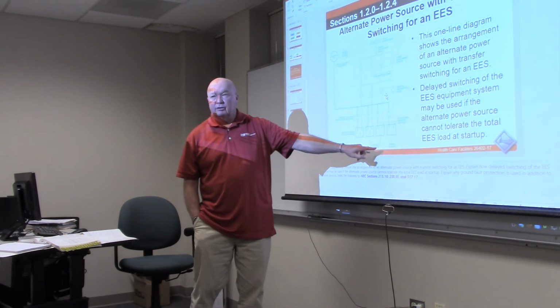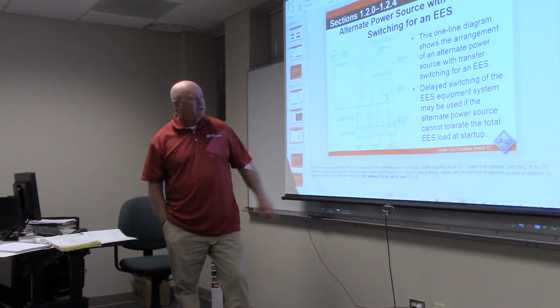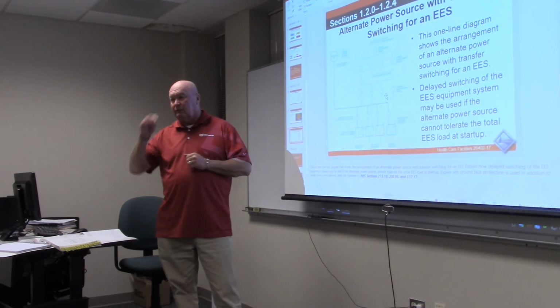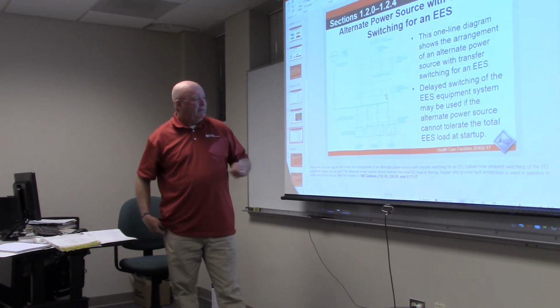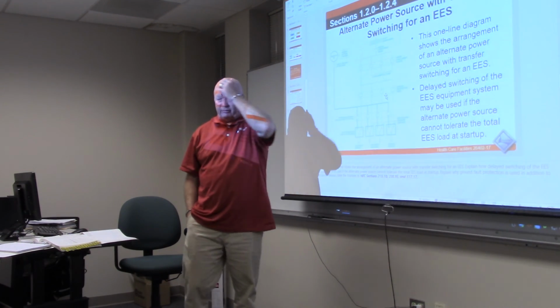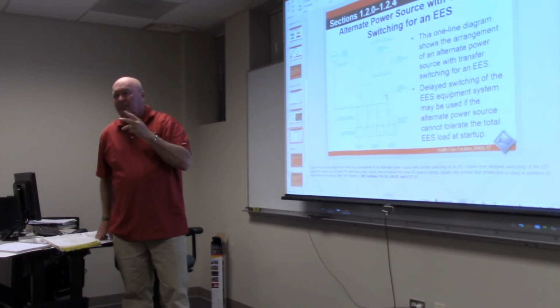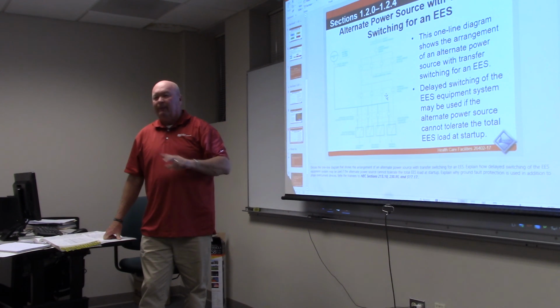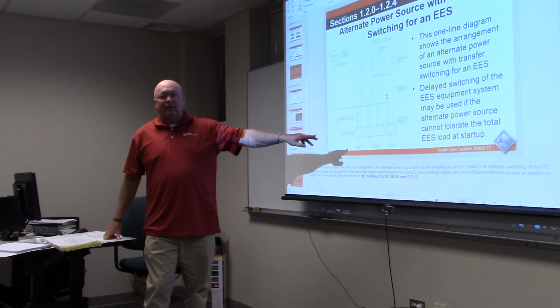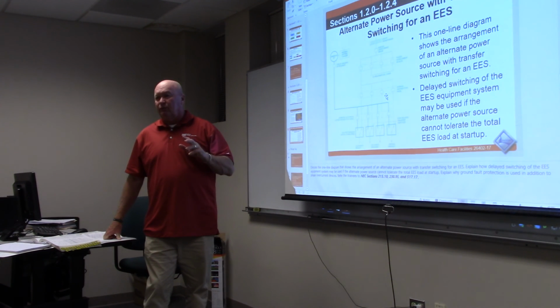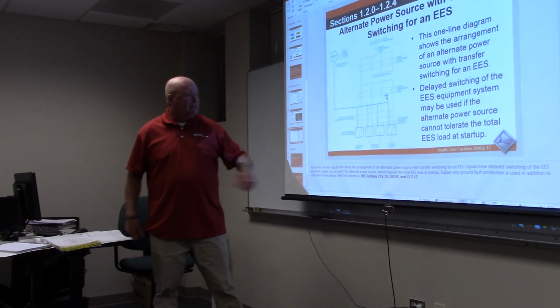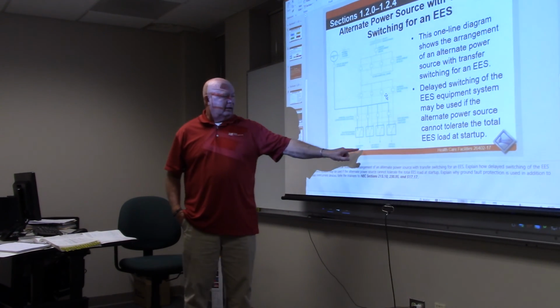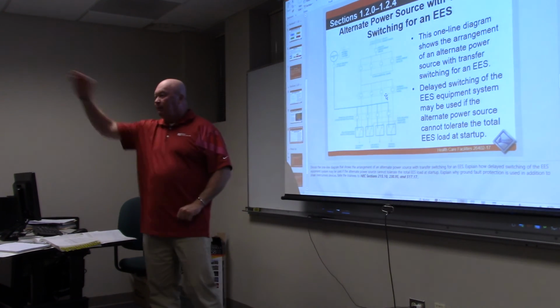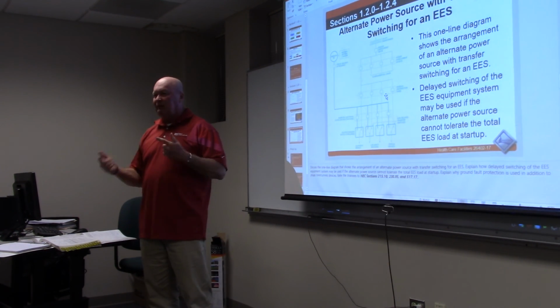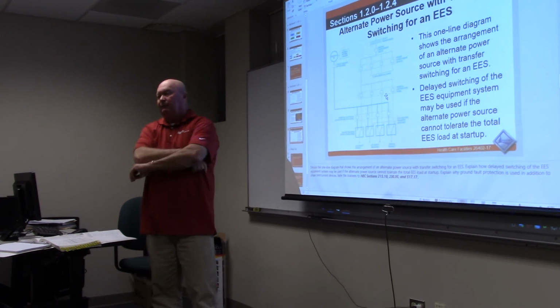But look here what they've done - they've broken this down into their 3 categories, haven't they? So you could have multiple transfer switches. Typically what I see as far as transfer switches, at a maximum there's usually 2: one for life safety, and the other for equipment, in installations we normally do since we don't do healthcare facilities. But even in an office environment, I see there's one for life safety and equipment, because life safety means what? What is life safety? Think about life safety inside of a building - what would that be in an office building?